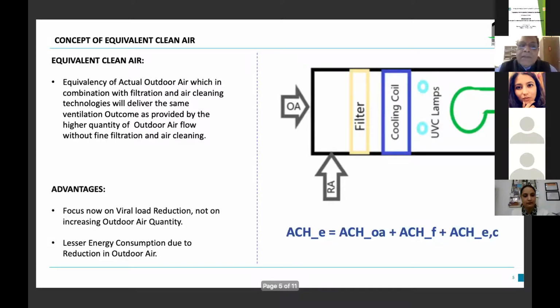So that 300 CFM becomes the equivalent of 1000 CFM of clean air, which you require if you are going by the normal approach of minimum outdoor air required. So it is an equivalency of actual outdoor air, which in combination with filtration and air cleaning technology will deliver the same ventilation outcome as provided by the high quantity of outdoor airflow without fine filtration and air cleaning. And you can see in the formula below, that is the ACH, the air changes per hour, the total indoor air replaced, the number of times in 1 hour.